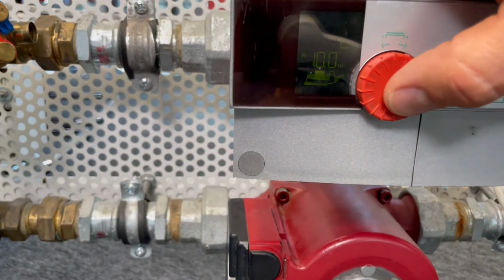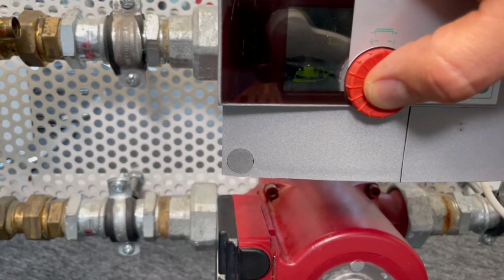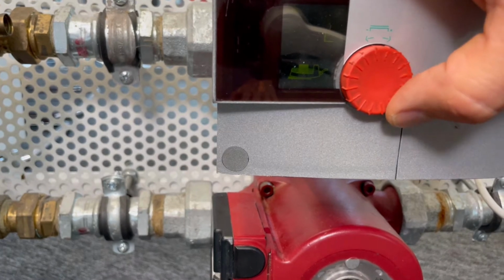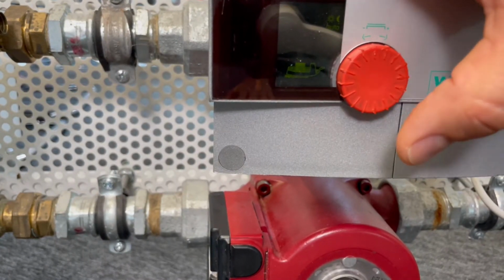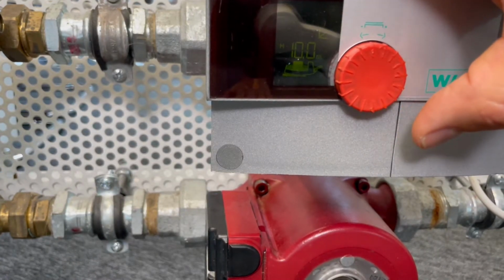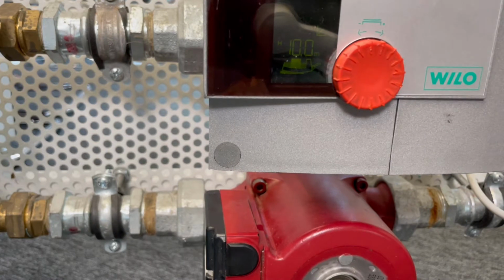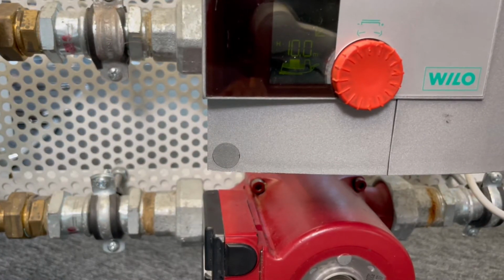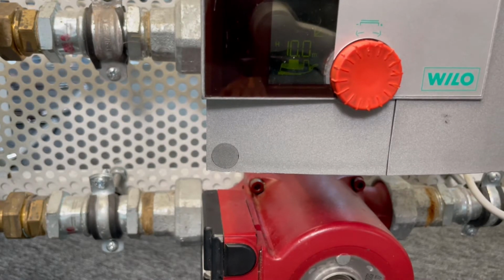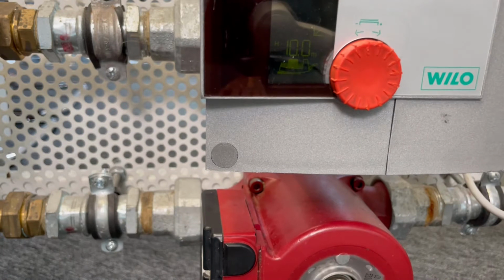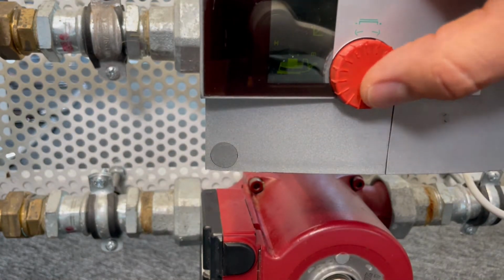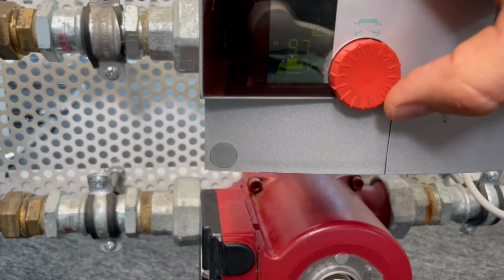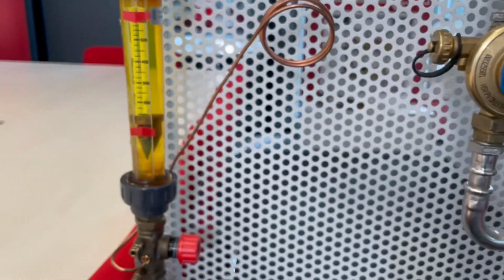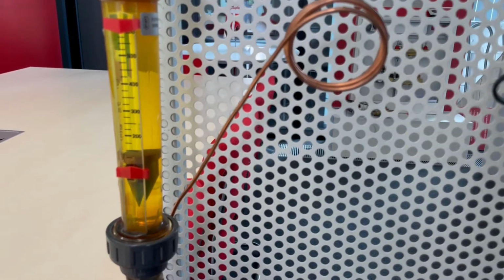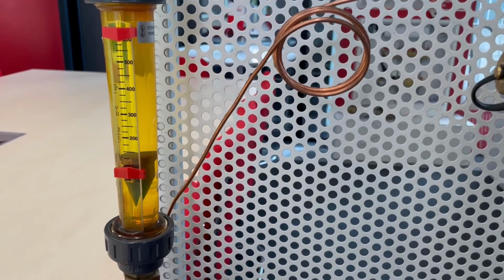Okay, so first what we do, we change the setting from constant to variable. We immediately hear that the pump noise is reduced, and it now works more quietly. We still have 100 in each riser, so I can go down with the pump. I go down with the speed of the circulation pump.